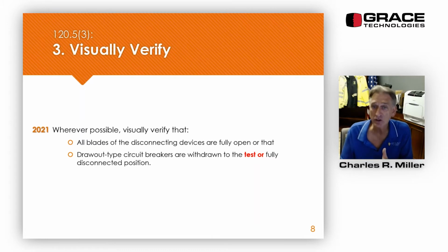120.5, number 3, visually verify. If it is possible, visually verify that the blades of the disconnecting device, safety switch or disconnect switch, are fully open, or if it's a draw-out type circuit breaker, make sure that it is withdrawn to the test or fully disconnected position. Now, where it says 2021 here and the words "test or" are bold, that was added in the 2021 edition of 70E. Before that, it just said make sure that it's withdrawn to the fully disconnected position. In my presentation, I'll show you what has changed from the 2018 to the 2021 edition of 70E.